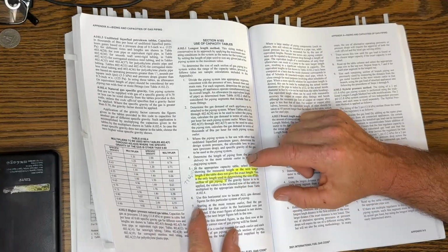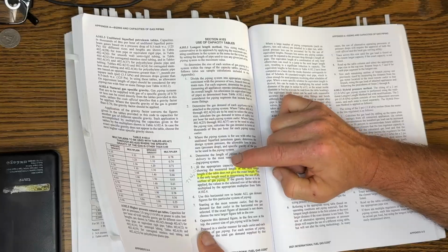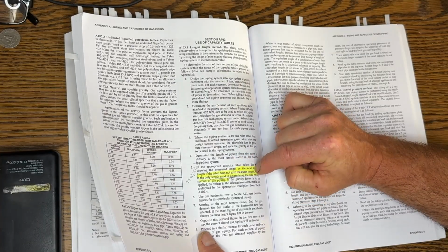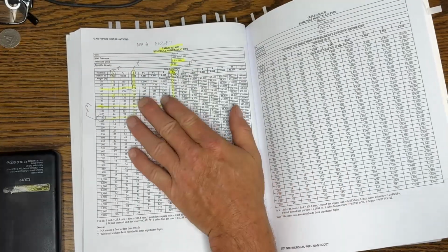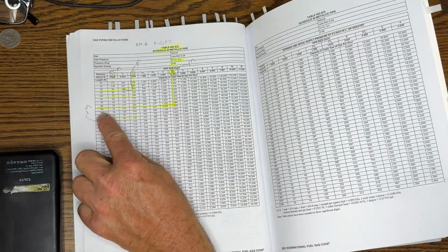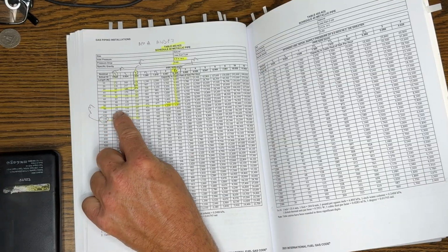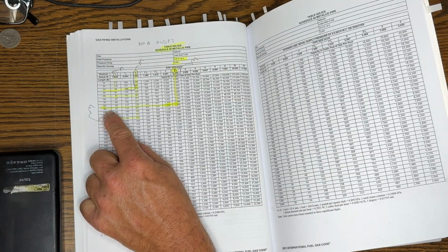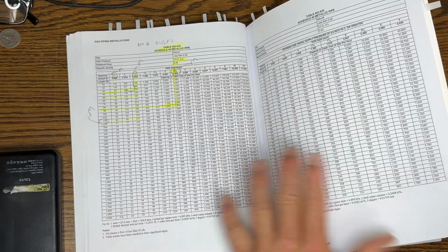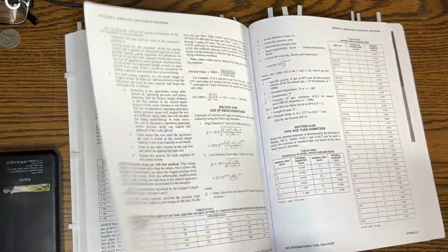So this is the table it's referencing, and this tells you how to interpret it. What you do is go to the next longer one. If the table does not give the exact length, the next longer length is the only length used in determining the size of any section of gas piping. So let's say you're 91 feet long and you had like 50, you've got to go to the next one is what I'm getting at. I don't want to take the time to think it through, but this tells you how to interpret that table.